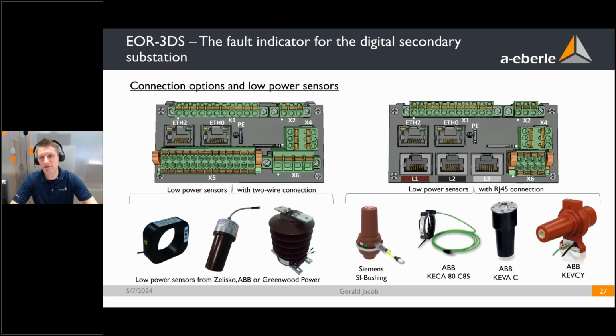Regarding sensors, we have different options. We have even wider range for sensors compared to the EOR-1DS. First, very comparable is shown here on the left side, so low power sensors with 2-wire connections. As I said before, at the EOR-1DS, there are different manufacturers like Zelisko, ABB, Greenwood Power that offer such sensors with 2-wire connection, class 0.5. And as you can see from the back of the EOR-3DS, you have a 26-pole terminal plug, X5, and here you can connect all your, in total, 4 voltage sensors and 4 current sensors if you want to.